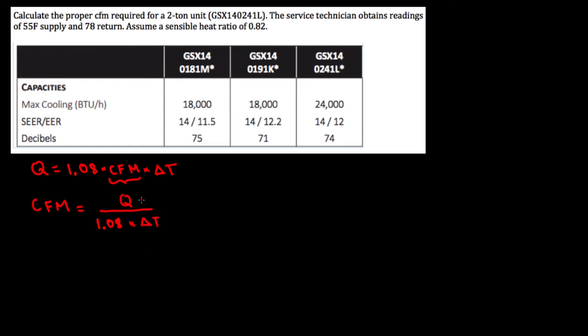In other words, if we want to obtain the CFM we need the sensible heat and we need the delta T. Let's start with the delta T. Delta T equals the temperature on the return side minus the temperature on the supply side. The return side temperature is 78°F and the supply side is 55°F, so delta T equals 23.